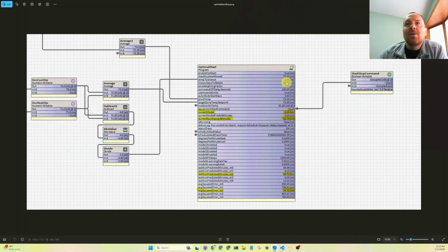So we're capturing that critical minutes required to recover the zone, then also the delta temperature here, which is this 73. Here's our zone temp. So this is the delta temperature that it takes to get that. So we're holding this data in an array: our delta temperature, and the amount of minutes, and then each one of these different models has a couple different ways of predicting minutes. And then currently our average squared error, model 2 is the best.